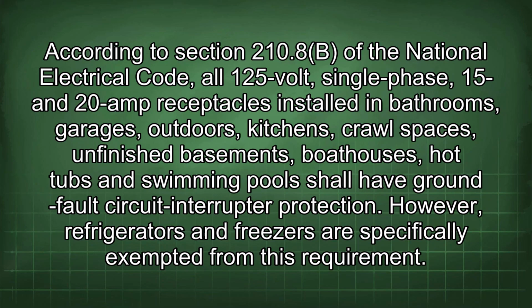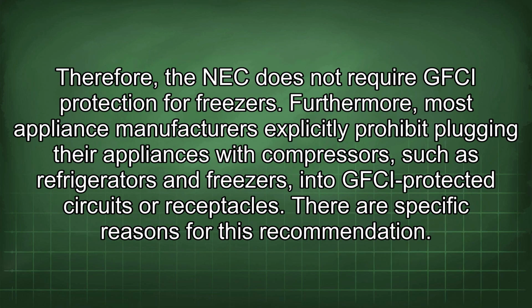According to Section 210.8(B) of the National Electrical Code, all 125-volt, single-phase, 15 and 20 amp receptacles installed in bathrooms, garages, outdoors, kitchens, crawl spaces, unfinished basements, boathouses, hot tubs, and swimming pools shall have ground fault circuit interrupter protection. However, refrigerators and freezers are specifically exempted from this requirement. Therefore, the NEC does not require GFCI protection for freezers.